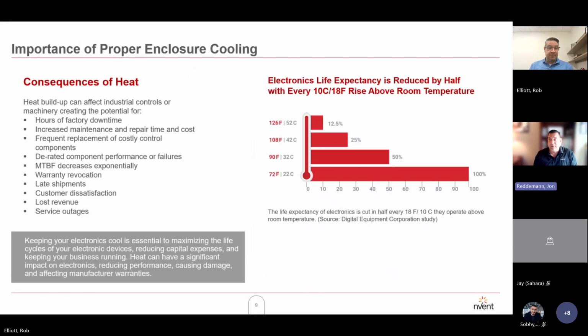So when we're talking about the importance of managing the heat loads in the enclosure, all of our components have a maximum temperature rating. I'll take a drive, for example. You'll see a drive rated at 50 C with potentially a 15% derate. That doesn't mean that we can operate at 50 C on a continual basis. The ideal temperature range for an industrial automation enclosure is really between 85 and 95. UL says that we can go up to 104 for design temperature before we have to submit for variance, right?